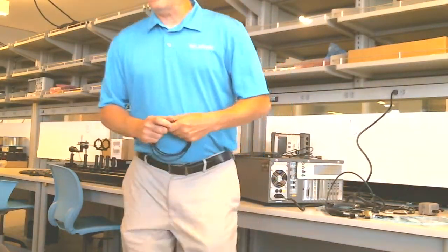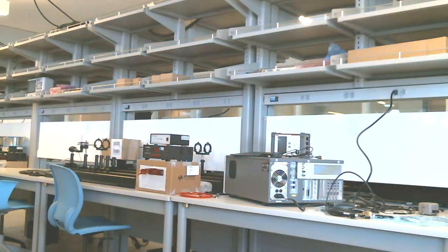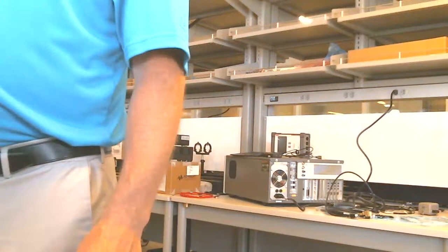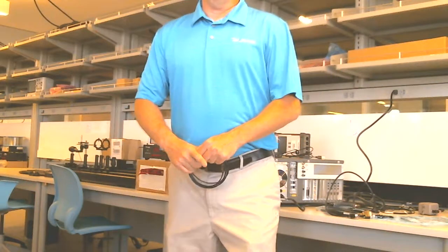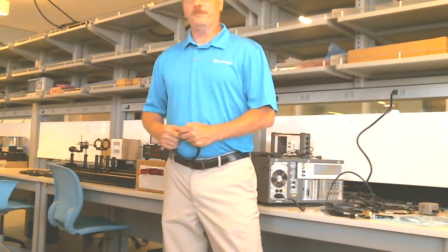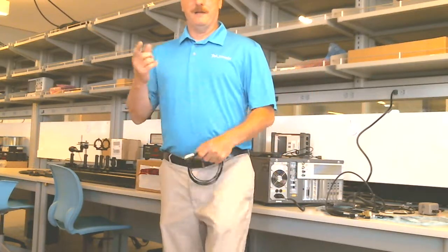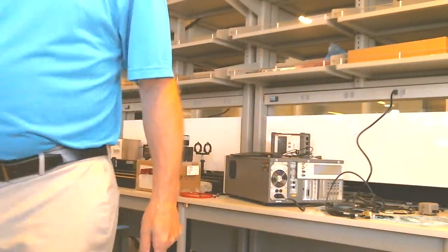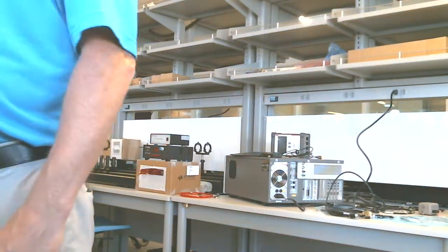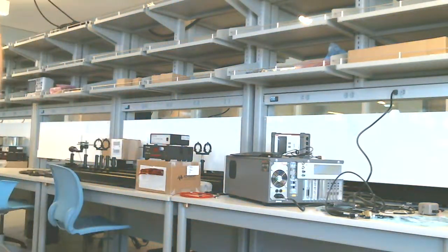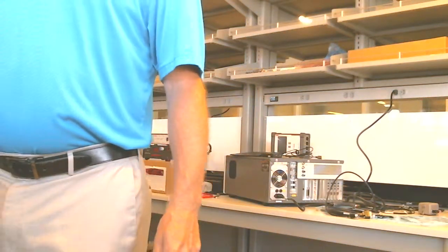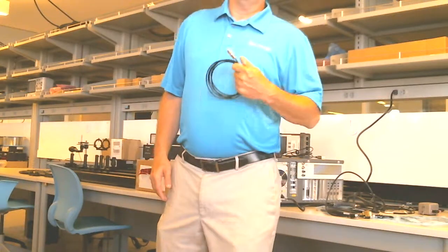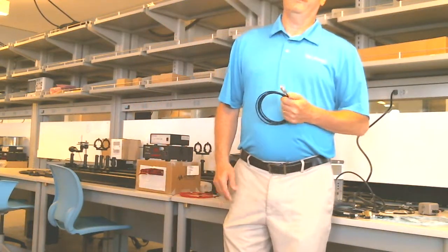You'll notice this guy doesn't have triax, it's got Phoenix connectors. So even though that's capable of measuring femtoamps, you're not going to measure femtoamps unless you buy an adapter that adapts from Phoenix to triax. If you buy, we have another version of this, the 2636, which has higher current sensitivity, we don't give you that option, we just put triax on it because you need triax to make very low current measurements.